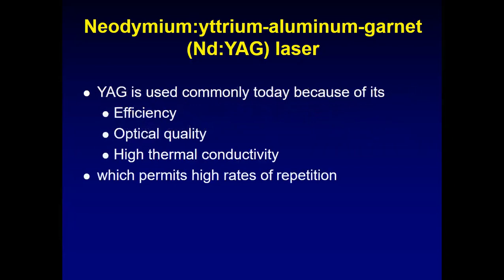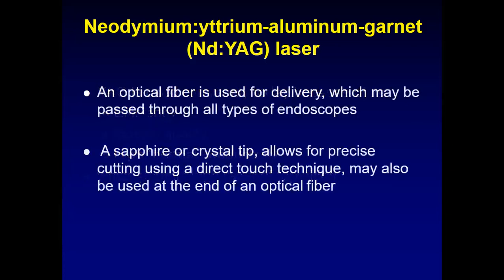YAG is the most commonly used crystal because of its efficiency, optical quality, and thermal conductivity, which permits you to repeat it continuously for more time. Otherwise, it can be damaging for the tissue and the machine as well. So an optical fiber is used for delivery, which may be passed through all types of endoscopes.